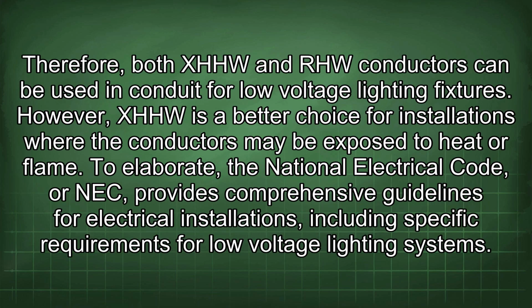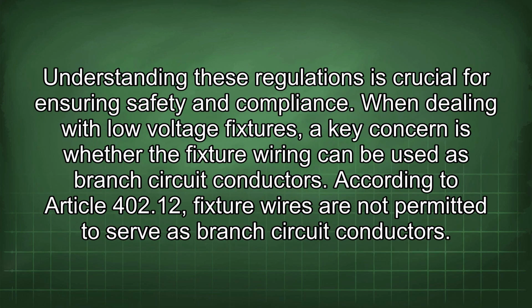Therefore, both XHHW and RHW conductors can be used in conduit for low voltage lighting fixtures. However, XHHW is a better choice for installations where the conductors may be exposed to heat or flame. To elaborate, the National Electrical Code, or NEC, provides comprehensive guidelines for electrical installations, including specific requirements for low voltage lighting systems. Understanding these regulations is crucial for ensuring safety and compliance.